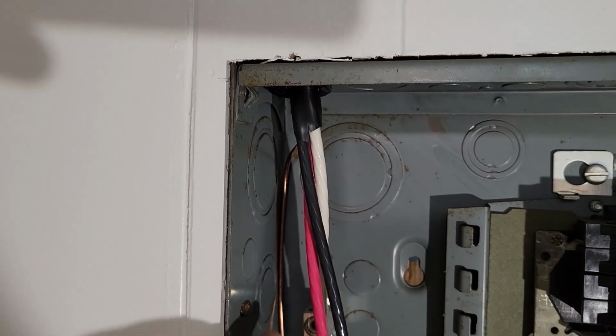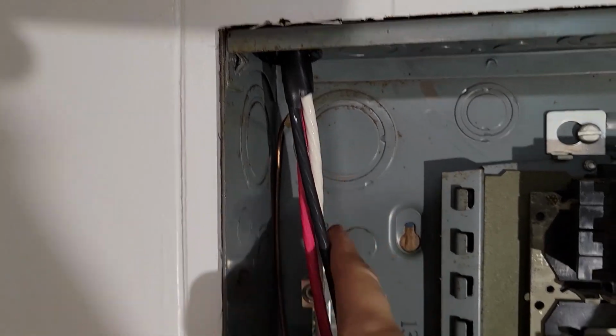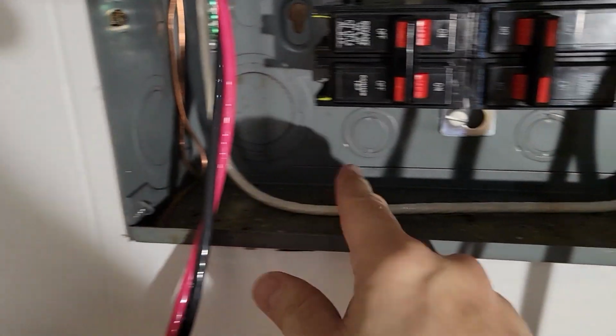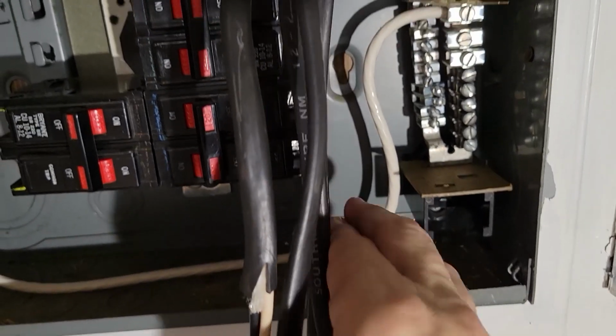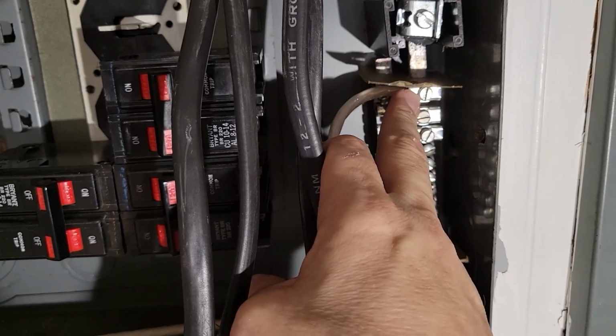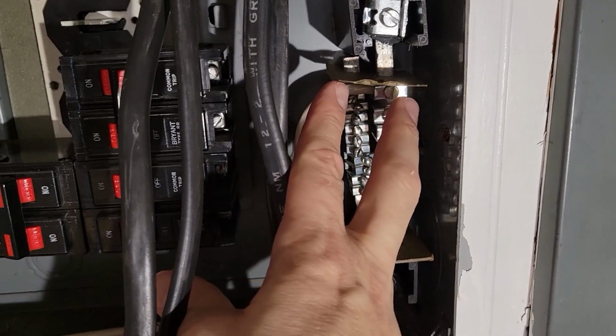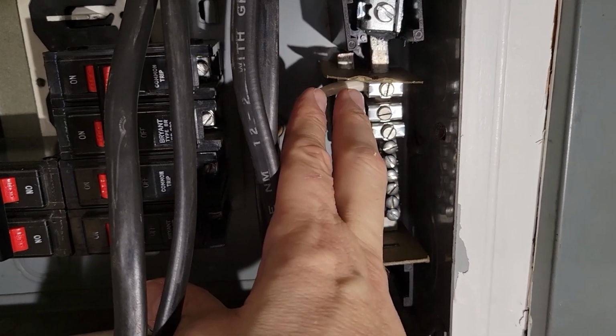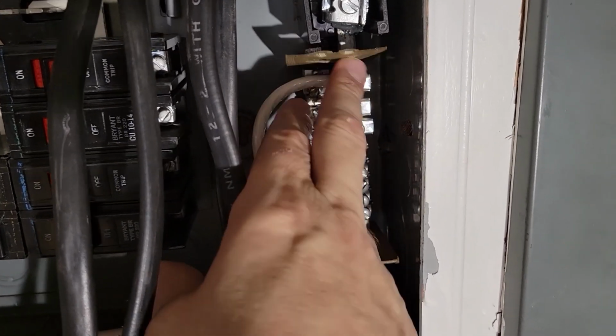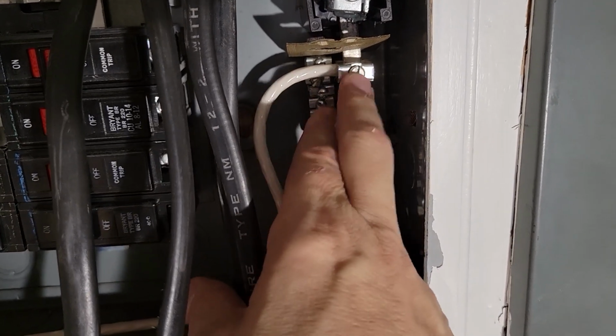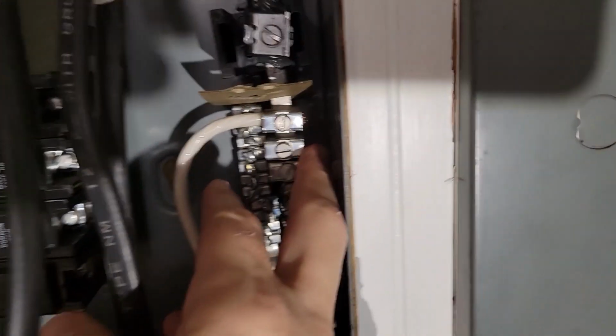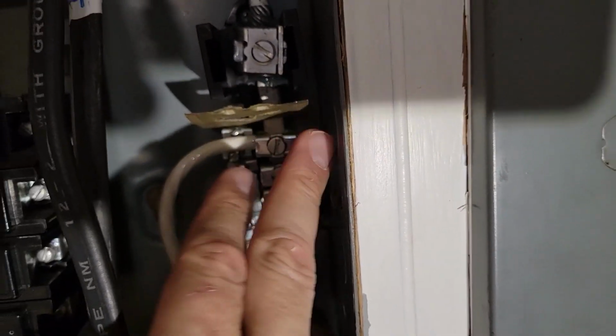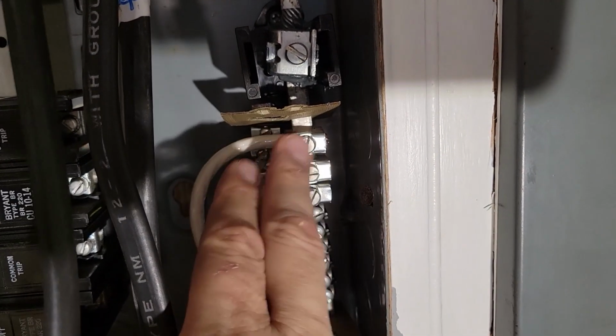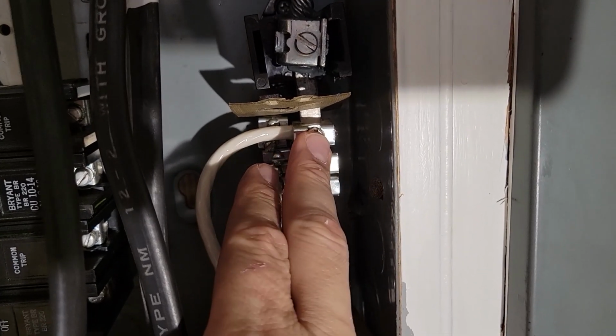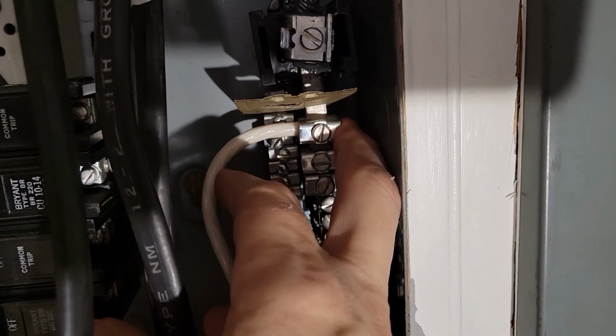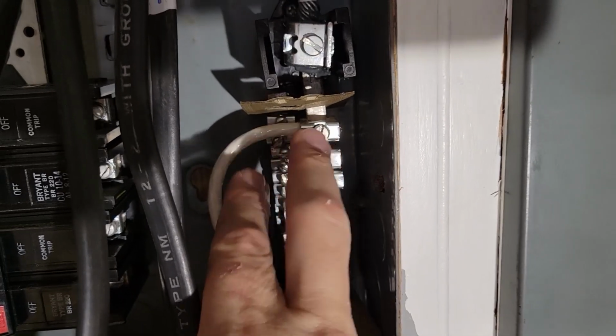So we did the ground first because you always do ground first. Then we did the neutral. I brought that down, put a curve on it, put another curve, brought it up, and then found a lug that I could put it into. I took off about 1/2 inch of insulation, put it through, tightened that down. If you have a torque specification, then you go for that. And just make sure it doesn't poke out and touch the box, because then you're going to be grounding your neutral, and you don't want to do that. So if it protrudes a little bit, that's fine, as long as it's not touching anything else.